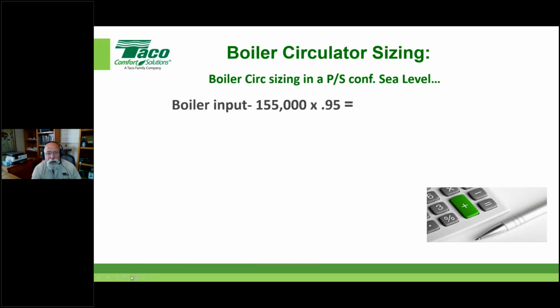So here it is, real quickly. Let's take the same 155 at a high efficiency AFUE of 95%. So here's the math on that. 147,250 is the result of this calculation here, divided by, just for teaching purposes, a 30-degree delta T. I take my 30 times 490 gives me my 14,700. So that result of this divided by this, anybody want to spit it out real quick? Most people doing TACO webinars have their calculator handy. What do we get? Anybody?